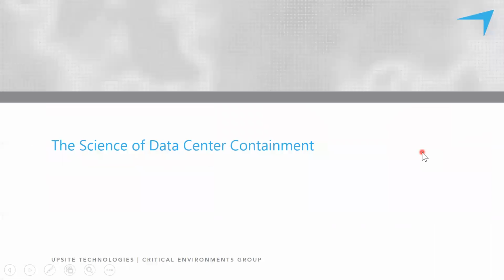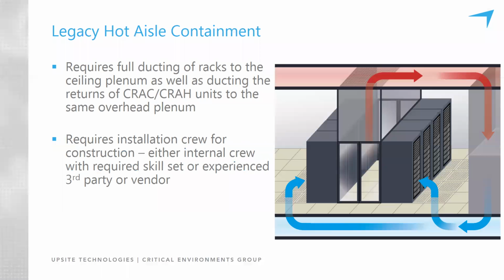So let's move into a little bit of the science of containment and show you some schematics of the airflow paths. Obviously, with legacy hot aisle containment, we're fully containing the hot air, ducting it to a ceiling plenum, and that is returning to the cooling units that have also been ducted to that ceiling plenum. So we're forcing this flow path through the room.